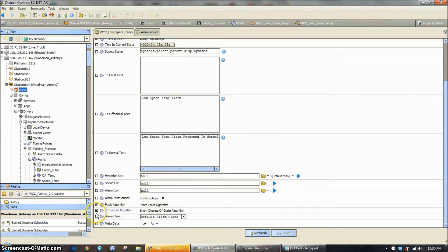As we go down to the bottom, really the only other thing to look at is the alarm class. In most systems, we only have set up a default alarm class and a critical alarm class. Critical alarm is set up to go to pagers and email, and default alarm class is just logged in the system — if you look at the alarm console, they're there, but we don't take any critical action on it. A low space temperature, high space temperature, high supply temp — those are all examples of default alarms. A critical alarm would be a freeze stat, a fire alarm, a smoke detector going off — something like that would be a critical alarm that you'd want to be emailed on.